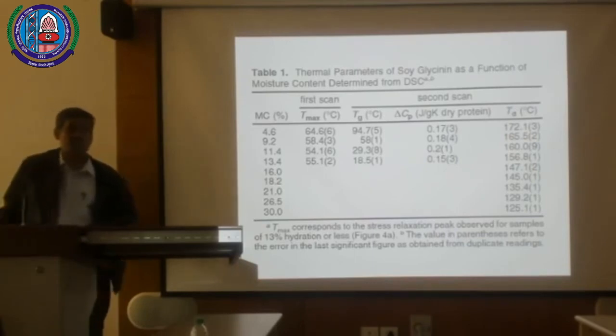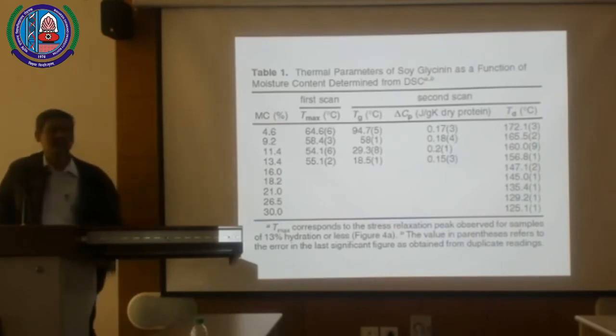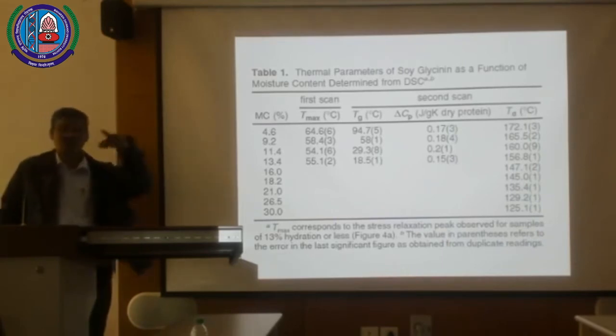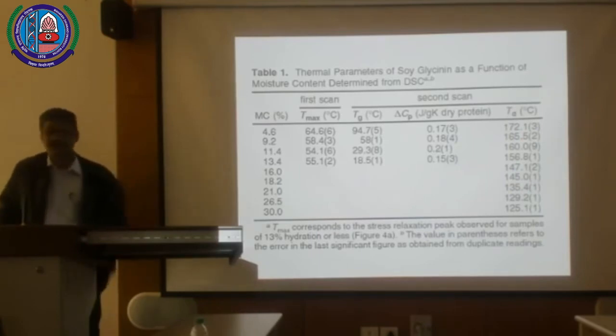For example, we have given the range between 20 to 40 degrees Celsius. The onset temperature would be 20, since it starts from 20. The end would be 40, the range we have given. The glass transition would come in between. Suppose 20 is the start and 40 is the end, then the middle will be 30. 30 will be our glass transition, and the endset point is 40.